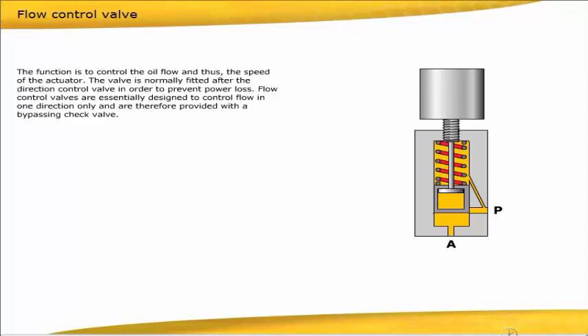Flow control valves are essentially designed to control flow in one direction only, and are therefore provided with a bypassing check valve. The direction of flow is from P to A. By moving the piston downwards, it will choke the oil flow.